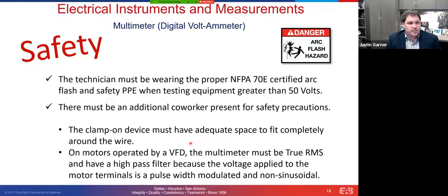A couple of other things to note. The clamp-on device, the amp clamps that I showed you a picture of earlier, need to have adequate space to fit completely around the wire. Oftentimes we get into very crowded or very tight electrical wiring compartments trying to measure amperage or voltage, and it's important that you can get a good solid clamp around those wires. Otherwise you can have a false reading on your amp clamps.